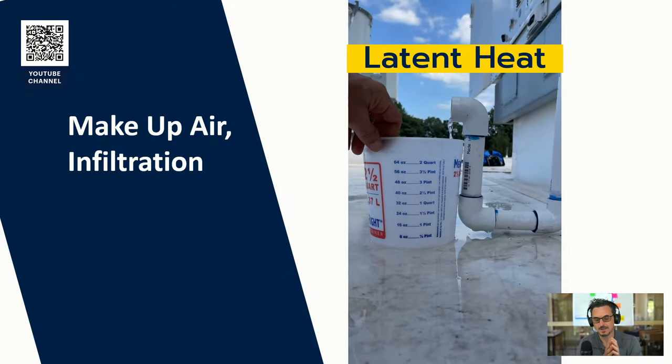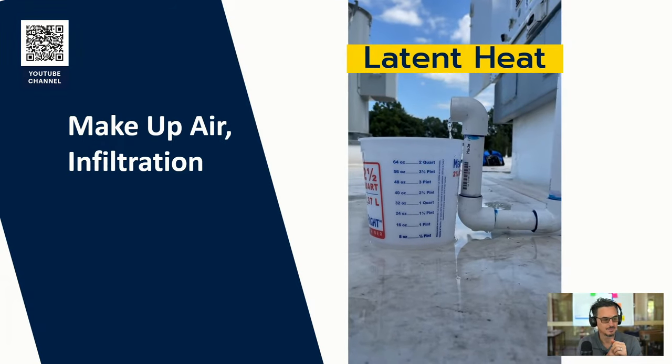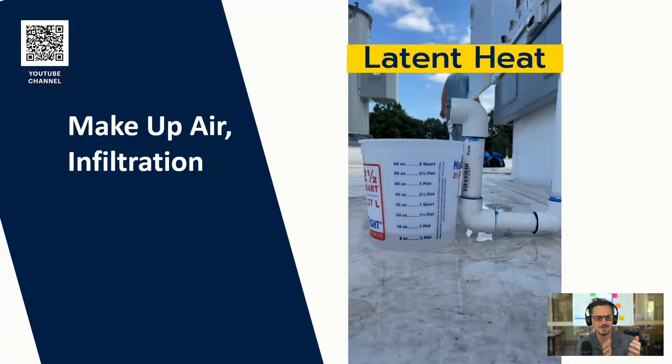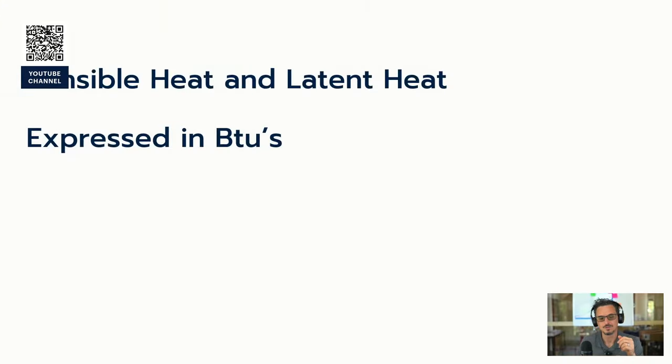I just like this video because it's that same unit. This is a 50-ton makeup air unit. There's two condensate drains off of this particular unit. It's amazing how much condensate, and this was a pretty dry day when we were out there on site not too long ago. A 50,000 square foot building could yield 1 to 10 gallons per minute of condensate during peak cooling times. And over a year, that could add up to 150 to 200,000 gallons of water savings. It really doesn't have a lot to do with this presentation, other than showing you how much moisture can come out of an outdoor airstream.